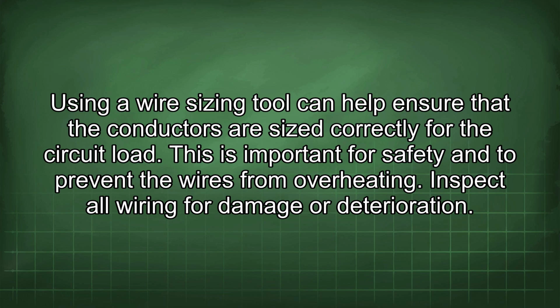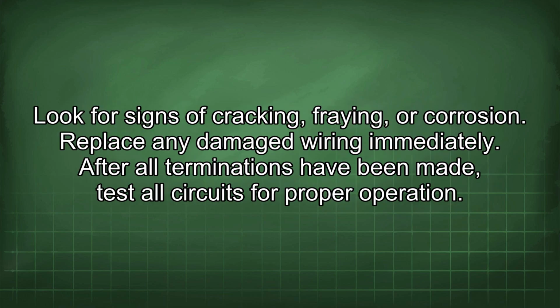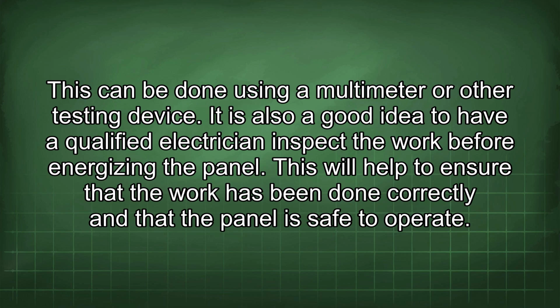Inspect all wiring for damage or deterioration. Look for signs of cracking, fraying, or corrosion. Replace any damaged wiring immediately. After all terminations have been made, test all circuits for proper operation. This can be done using a multimeter or other testing device. It is also a good idea to have a qualified electrician inspect the work before energizing the panel. This will help to ensure that the work has been done correctly and that the panel is safe to operate.